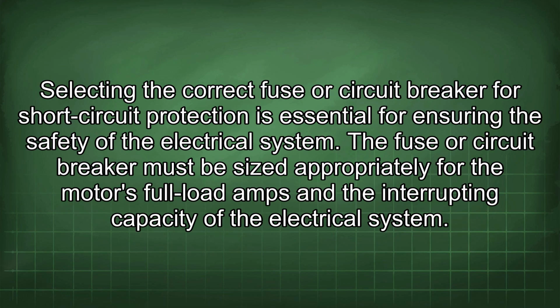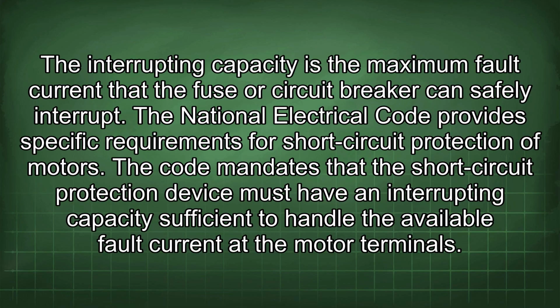Selecting the correct fuse or circuit breaker for short-circuit protection is essential for ensuring the safety of the electrical system. The fuse or circuit breaker must be sized appropriately for the motor's full load amps and the interrupting capacity of the electrical system. The interrupting capacity is the maximum fault current that the fuse or circuit breaker can safely interrupt. The National Electrical Code provides specific requirements for short-circuit protection of motors.